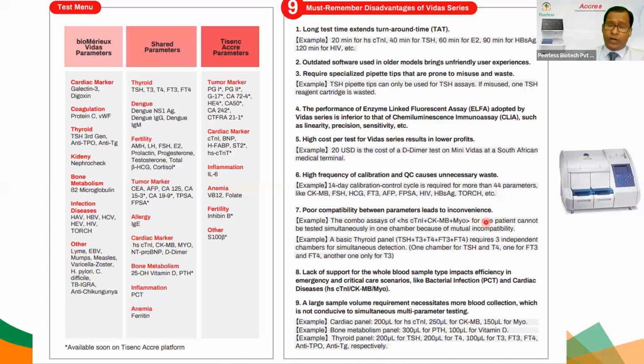It has 4 slots. But Minividas per se is a pretty old analyzer. So different kits were developed at different times, so the protocols of different tests are different. Say, for example, you want to run TSH, T3, T4, FT3, FT4. It requires 3 independent channels. Why? Because the protocol of TSH and T4 is the same, but FT3, FT4 and T3 protocols are different. And again, FT3 and FT4 protocols are the same, and T3 protocol is different. So in one channel, you have to run TSH and T4. For another channel, you have to run FT3 and FT4.